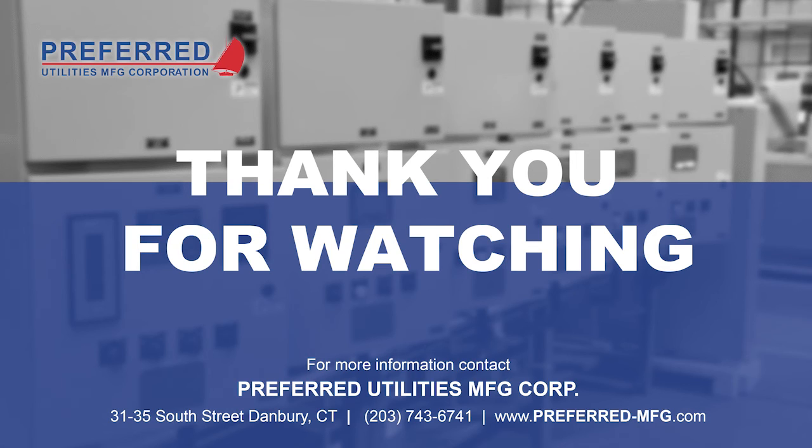Next question, what are the two solenoid valves for on the flow control manifold? The two solenoid valves are basically a belt and suspenders approach. You can get by with just one normally closed solenoid valve that is energized by the pump controls system. I was on a job last week that had two normally closed solenoid valves energized by the pump controls, just for redundancy.